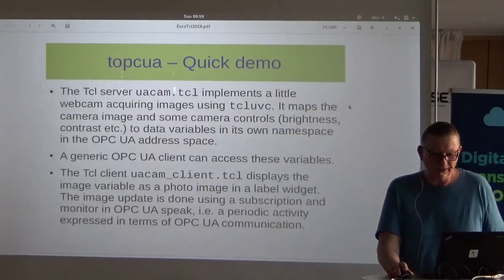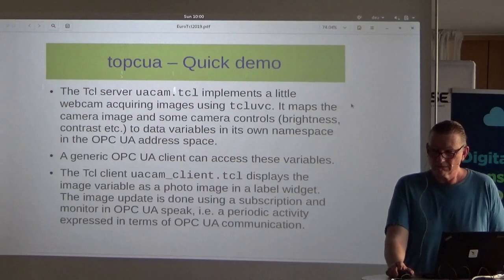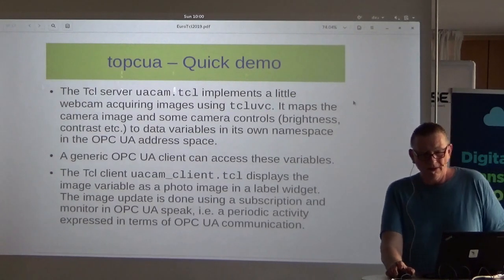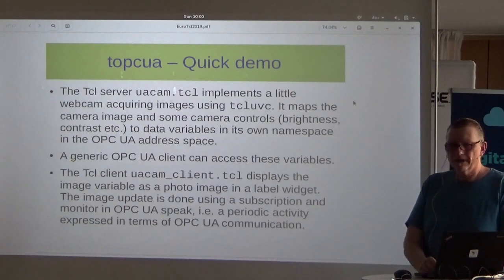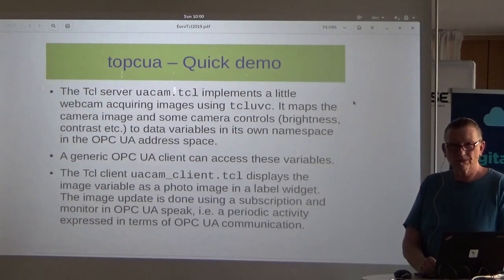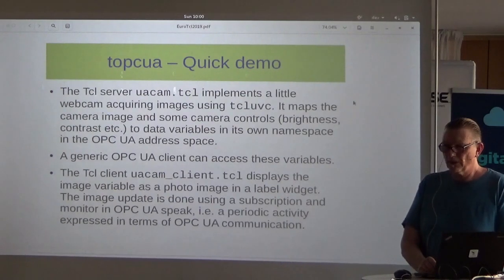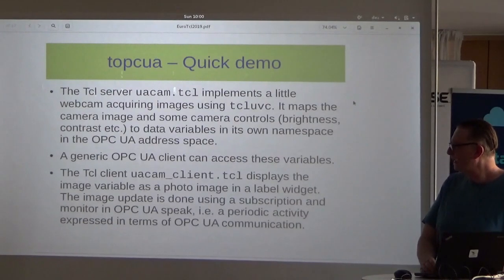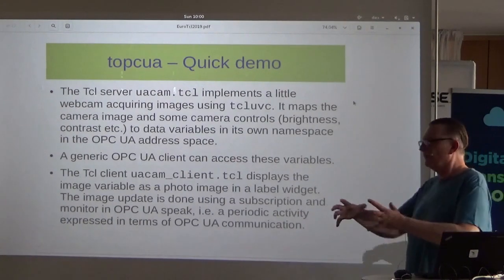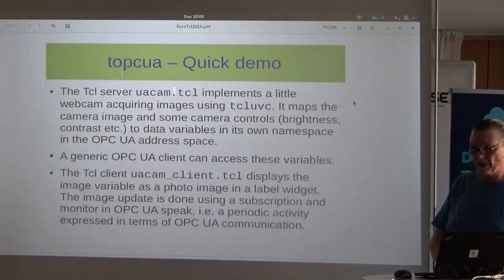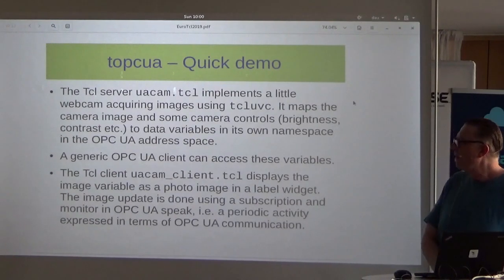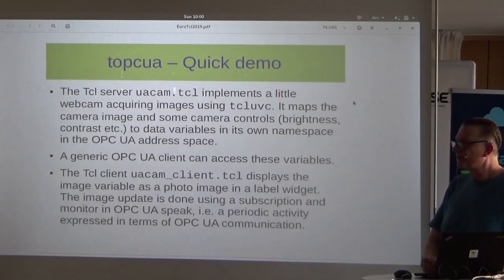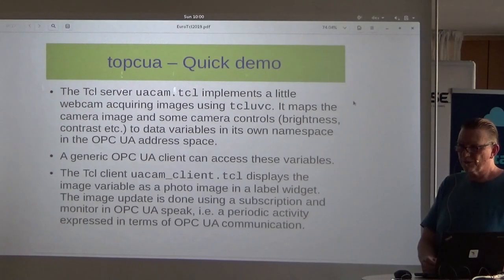OPC UA is the follower of OPC DA. It's a standard for machine-to-machine communication, about 10 to 12 years old, used for process control and automation. Like its predecessor OPC DA, it models a process as an address space with named variables, objects with methods, and so on. It resembles web services and SOAP, but uses a binary transport.